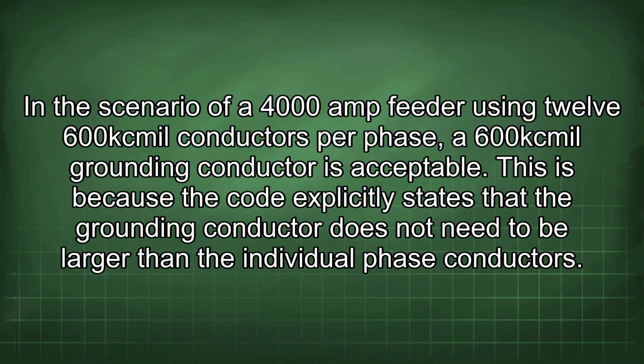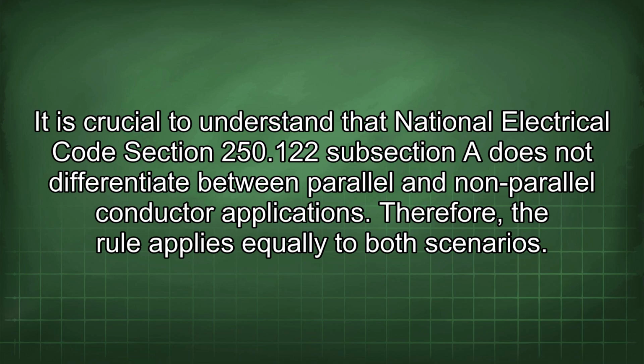In the scenario of a 4000 amp feeder using 12 600 kcmil conductors per phase, a 600 kcmil grounding conductor is acceptable. This is because the code explicitly states that the grounding conductor does not need to be larger than the individual phase conductors. It is crucial to understand that National Electrical Code Section 250.122 subsection A does not differentiate between parallel and non-parallel conductor applications. Therefore, the rule applies equally to both scenarios.